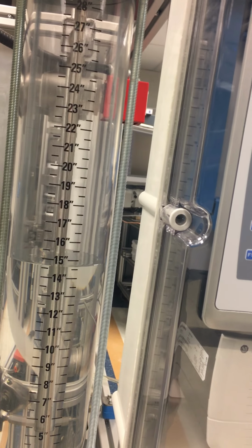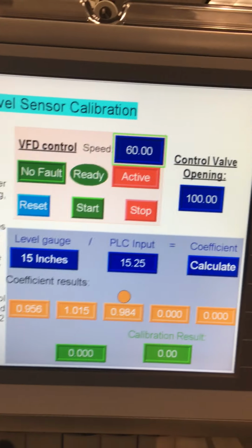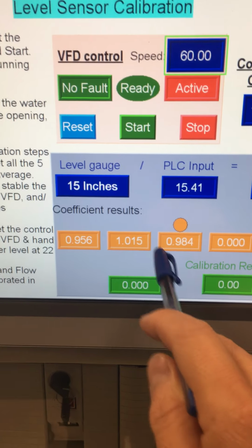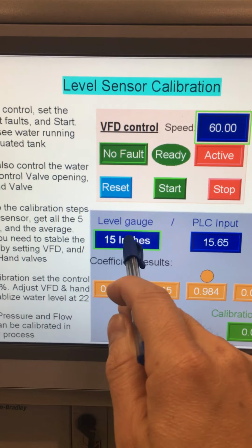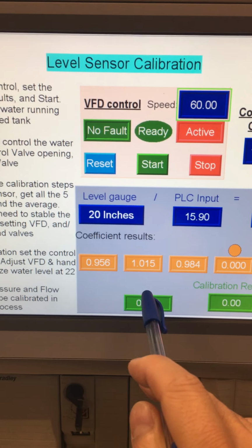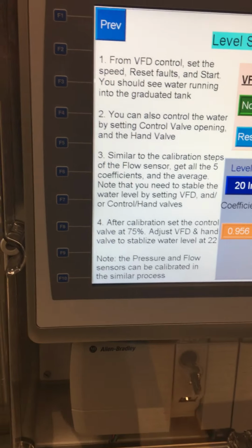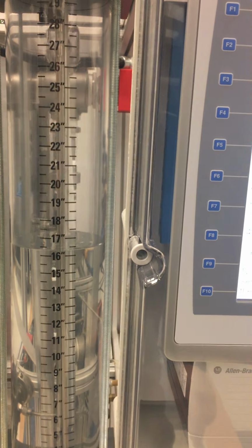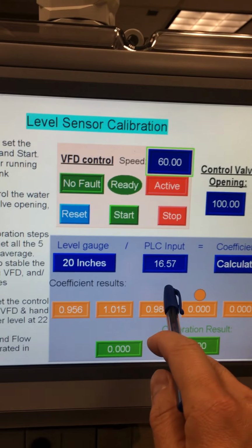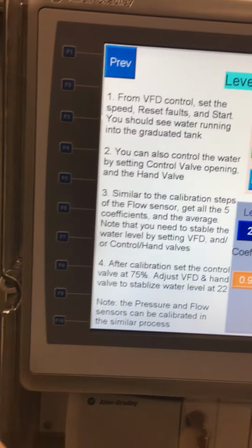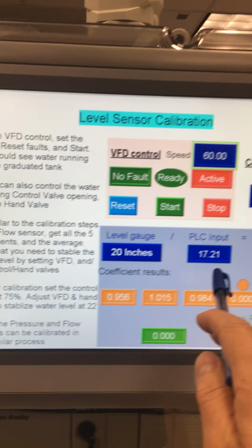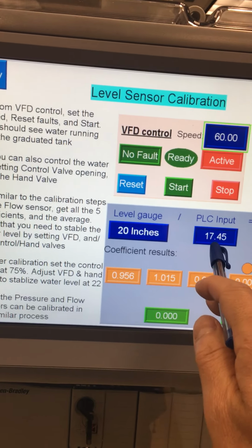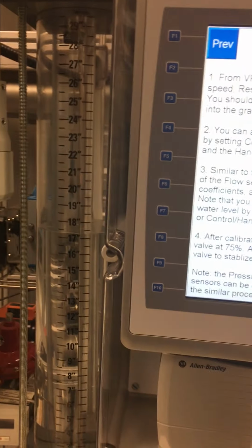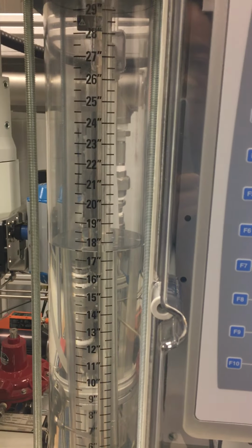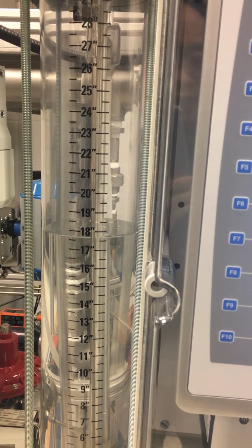Almost there. Once we reach 15, calibrate. So you can see the third result. And if we look at the next target, it'll be 20 inches, this one. So you can see the PLC reading is roughly there, reading almost 17 inches, yes, 17.